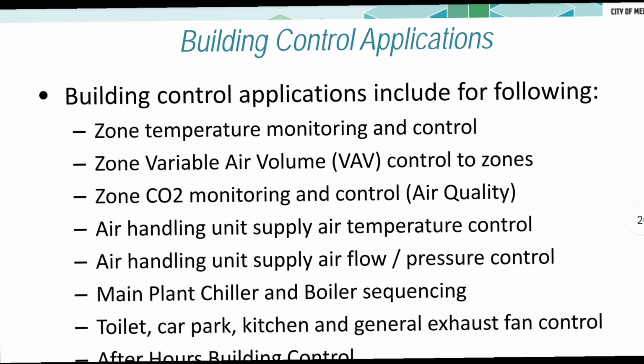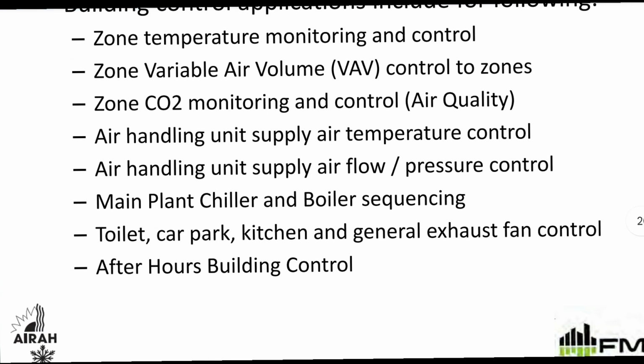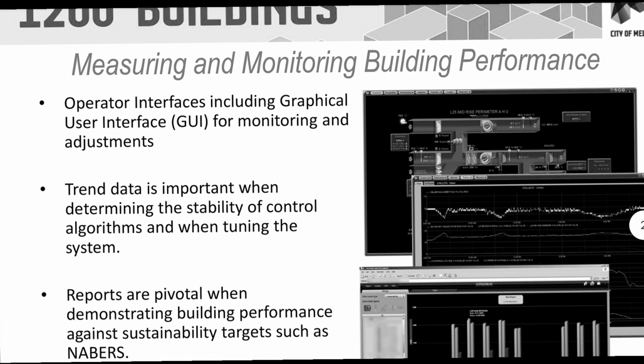Building control applications include the following. First, zone temperature monitoring and control. Second, zone variable air volume control to zones. Next is zone CO2 monitoring and control for air quality. Next, air handling unit supply air temperature control. Next, air handling unit supply airflow pressure control. Next, main plant chiller and boiler sequencing. Next, toilet, car parking, kitchen and general exhaust fan control. And after-hours building control.